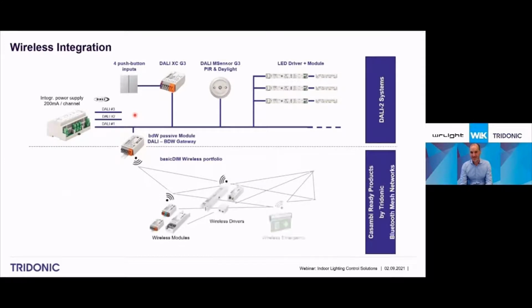Our basicDIM wireless portfolio includes Casambi ready products by Tridonic. We have Casambi as a partner, and a quite big portfolio of products developed and manufactured by Tridonic that go into luminaires, up to components for in-track drivers with wireless integrated, and emergency gears with wireless integrated. All these devices can now be connected through what we call a DALI gateway - really a Bluetooth to DALI gateway. This device translates the Bluetooth signals from the mesh network, the Casambi ready basicDIM wireless network, into DALI 2 signals on the DALI line.